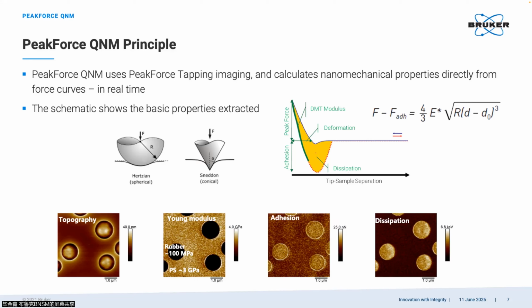It compresses the sample, and we measure the force, and we capture the deformation of the sample. And from that, we use the classic Hooke's law to get the stiffness out. And then with the help of the great Hertz model, we can calculate the modulus from the stiffness we measured. And that's the whole idea of AFM-based nanomechanics.